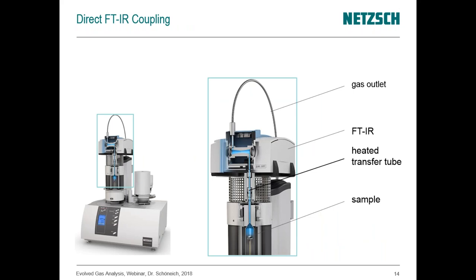The direct coupling is similar but a little different. The FTIR spectrometer sits on top of the furnace outlet with only a very short transfer line — around 10 centimeters — limiting the volume and reducing the condensation possibility. Nevertheless, this short section must still be heated in the same way as the furnace outlet and the FTIR cell.